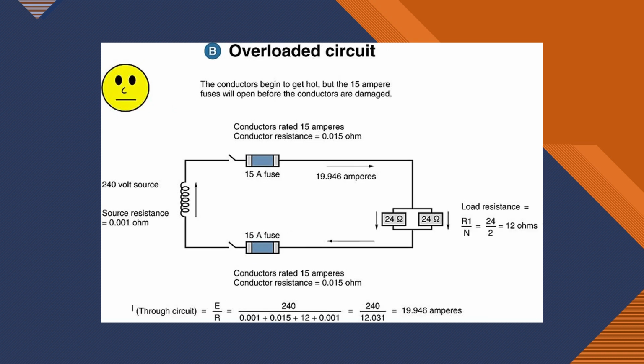Then I have an overload condition where I have added another load. I've increased my amps to 19.96. I've only got a 15 amp fuse. At some point that fuse, that overcurrent protection, is going to open and protect those conductors. These conductors are starting to get hot, and that is an overload circuit.